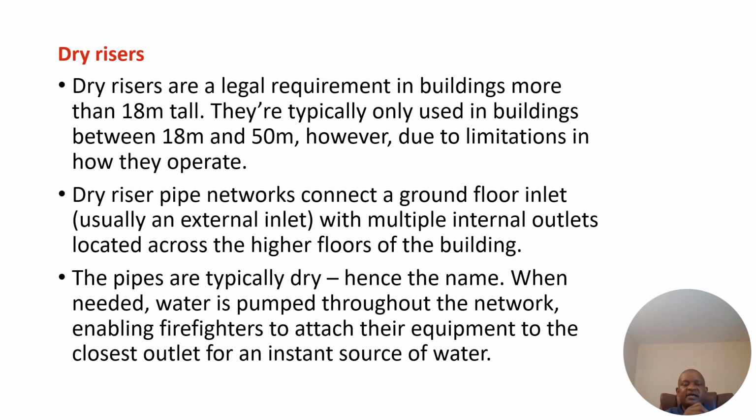Dry risers are a legal requirement in buildings more than 18 meters tall. They are typically only used in buildings between 18 meters and 50 meters, due to the limitations in how they operate.